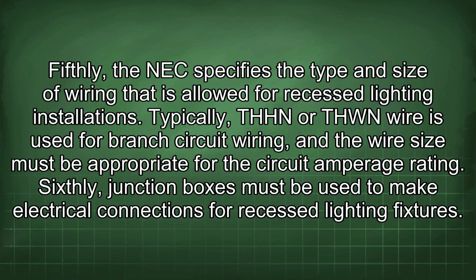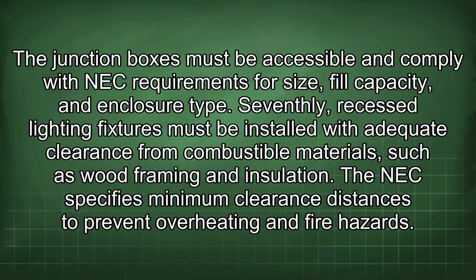Fifthly, the NEC specifies the type and size of wiring that is allowed for recessed lighting installations. Typically, THHN or THWN wire is used for branch circuit wiring, and the wire size must be appropriate for the circuit amperage rating. Sixthly, junction boxes must be used to make electrical connections for recessed lighting fixtures. The junction boxes must be accessible and comply with NEC requirements for size, fill capacity, and enclosure type.